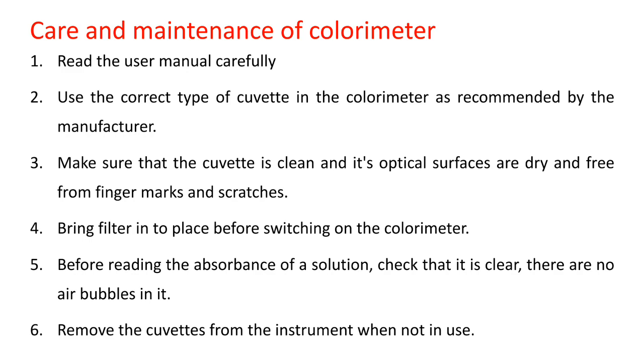Always read the user manual carefully before operating the instrument, and use the correct type of cuvette recommended by the manufacturer, and make sure that the cuvette is clean and its optical surfaces are dry and free from finger marks or scratches. Bring the filter in place before switching on the colorimeter, based on the color of your solution.